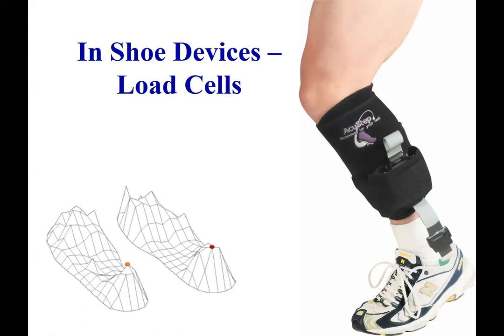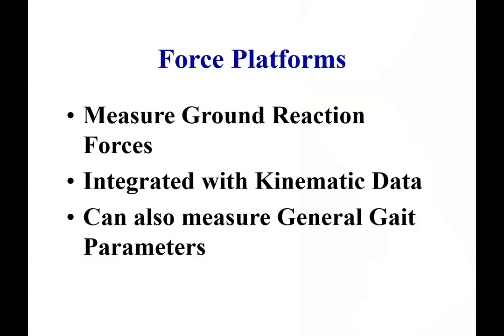Force platforms are the best option for measuring forces — piezoelectric-based platforms are considered better than strain gauge-based ones. They measure ground reaction forces: how much pressure, in what direction, and what the peak is when the person puts their foot down. This kinetic data can be integrated with kinematic angle data on the computer. Phase-by-phase percentage data, cadence, velocity, stride length, and step length can all be calculated.